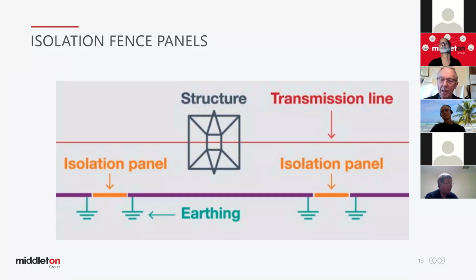Whereas, as I understand it, another way, especially in an urban area, would be to run an aerial earth wire between the transmission towers. What's your view on that? Well, yes, that could be part of the design. Just to address the first part of your question, you're right. When we're looking at some secondary mitigation like isolation panels, or there's even a case I was talking about doing a special design, a halo, a substation, or even when we do what we call separated designs, they're a little bit special, and the danger with them is that they can be corrupted by an individual coming along and thinking they're doing the right thing by stringing a bit of stainless across here to put a passion fruit vine on, or installing an LV light fitting that's got to be earthed, and it corrupts your design. So that's things we have to look at when we do these special designs.